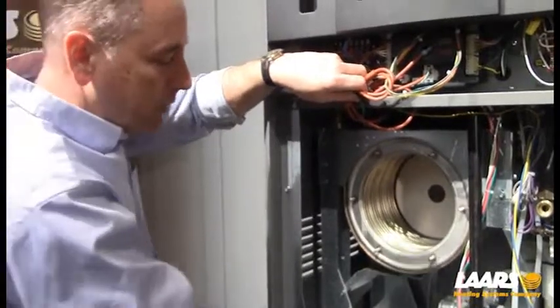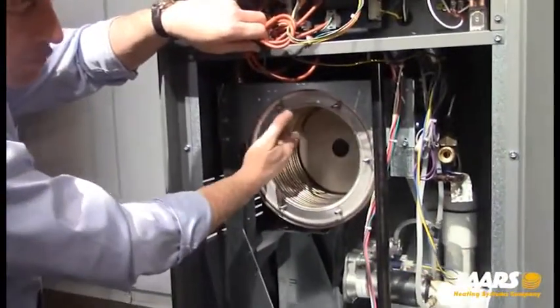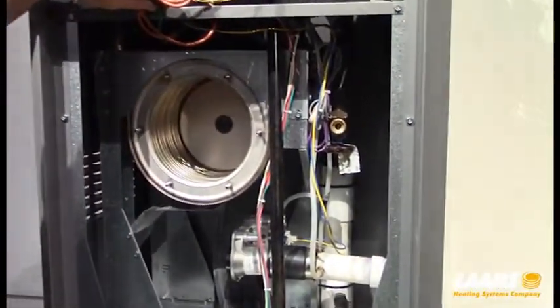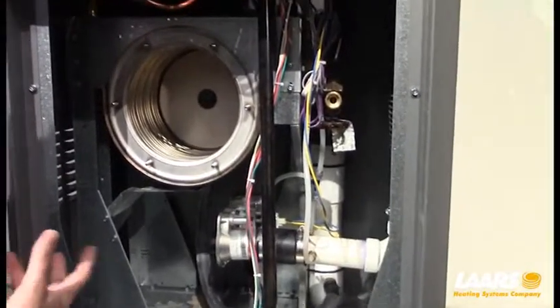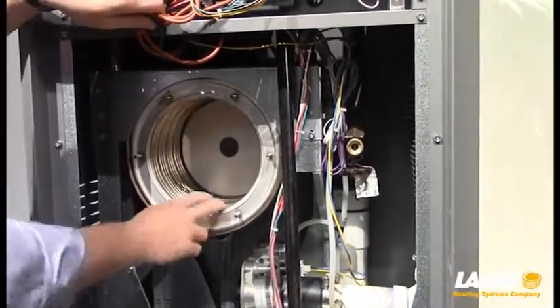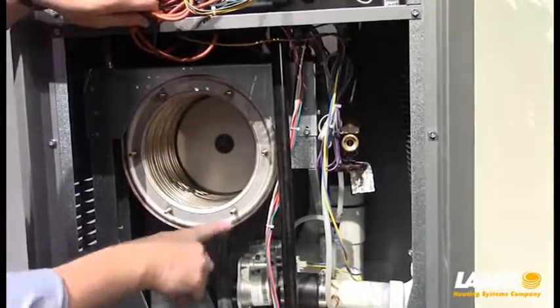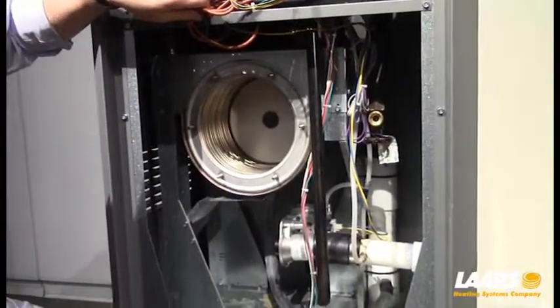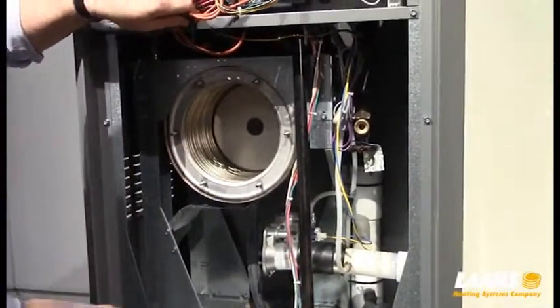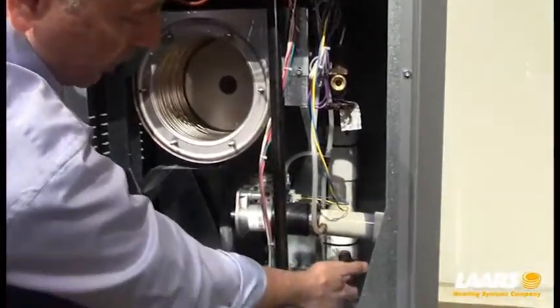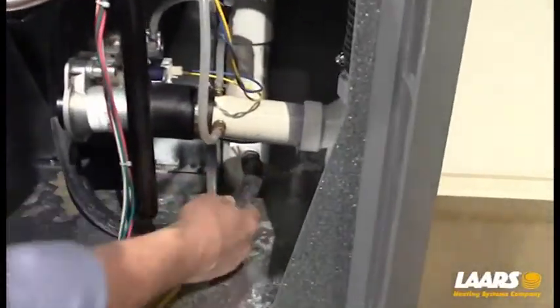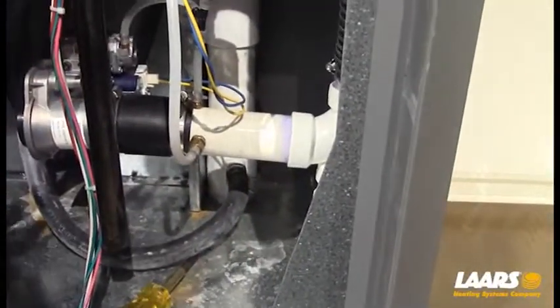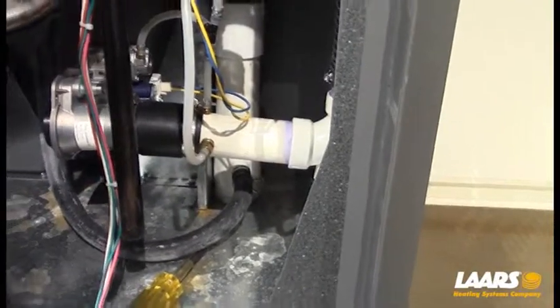Do not use a steel brush. This is a stainless steel heat exchanger. We do not want to score it or gouge it. Okay. Any other debris, try and vacuum it out, and then you can wash the balance down through the condensate. Just make sure if you do have a lot of debris, you want to remove the condensate hose from the condensate trap. That way you do not get a lot of debris caught up in the condensate trap.